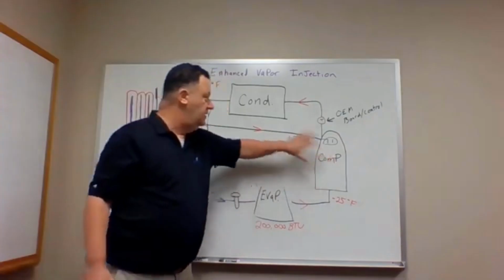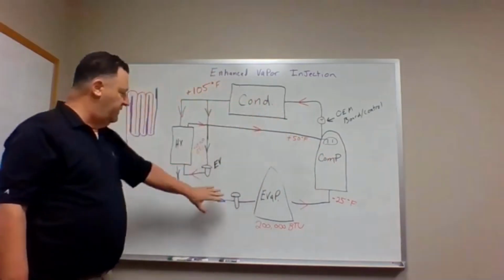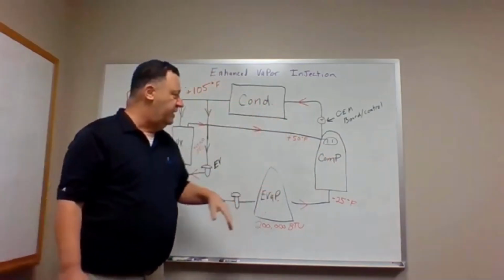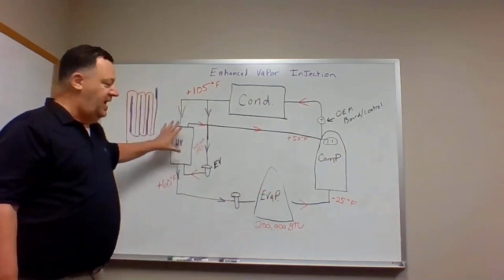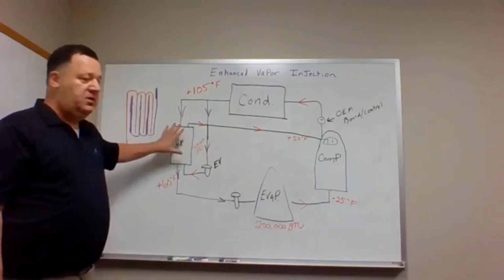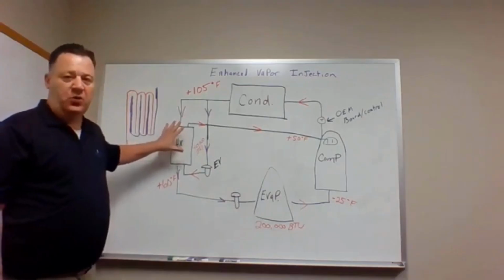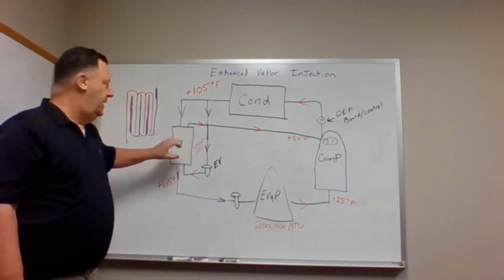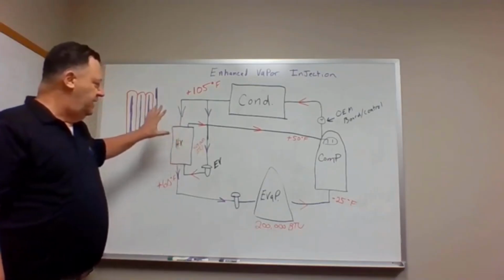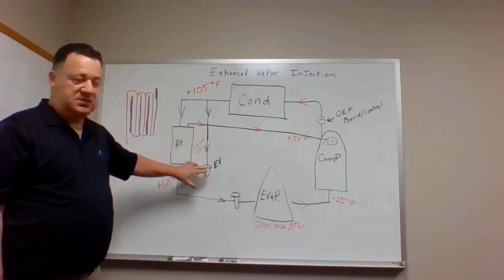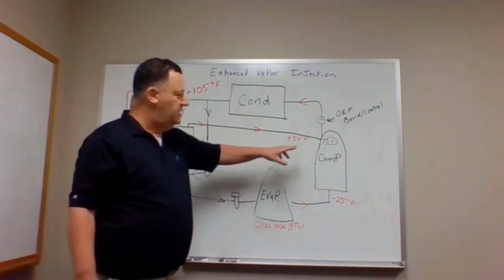We've got the compressor, we've got the condenser, we have a metering device, and we have an evaporator. Now, what I've added over here is what we call a heat exchanger, and I'll explain that a little more in depth as we move along, okay? And I've got an EV here also, and I'll talk a little bit about that. So let's walk through the compressor.